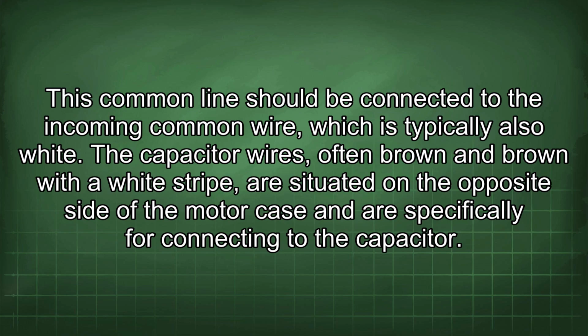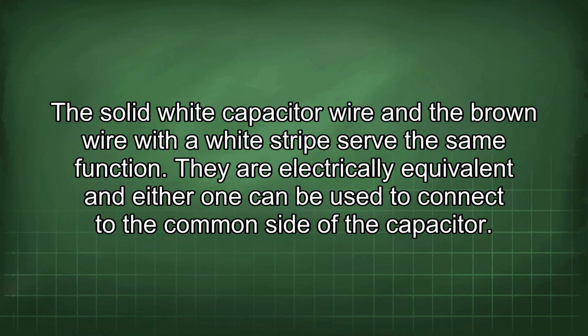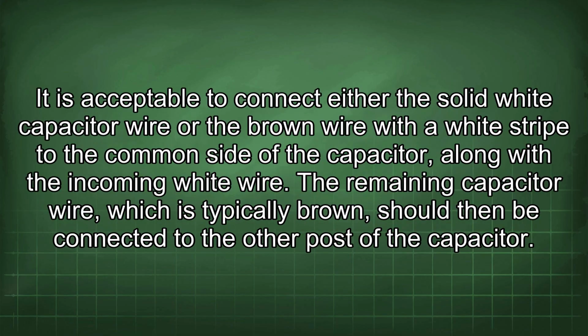The capacitor wires, often brown and brown with a white stripe, are situated on the opposite side of the motor case and are specifically for connecting to the capacitor. The solid white capacitor wire and the brown wire with a white stripe serve the same function. They are electrically equivalent, and either one can be used to connect to the common side of the capacitor. It is acceptable to connect either the solid white capacitor wire or the brown wire with a white stripe to the common side of the capacitor along with the incoming white wire. The remaining capacitor wire, which is typically brown, should then be connected to the other post of the capacitor.